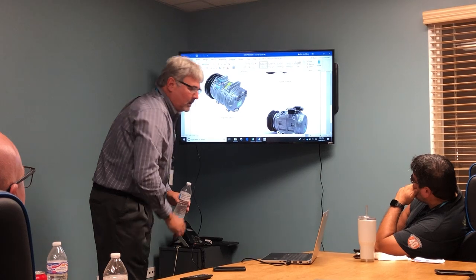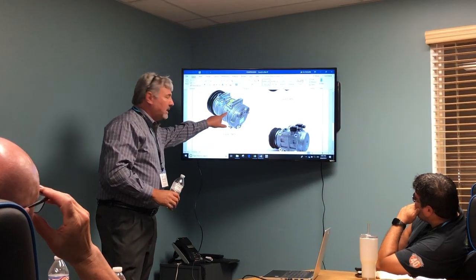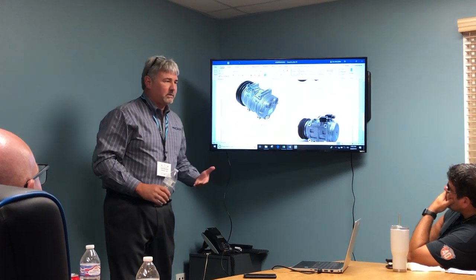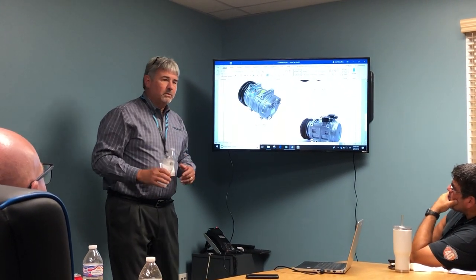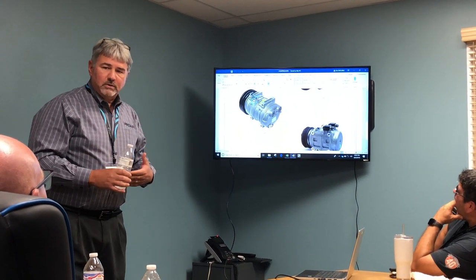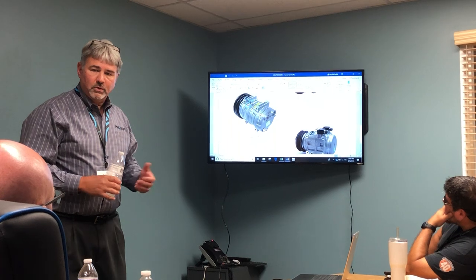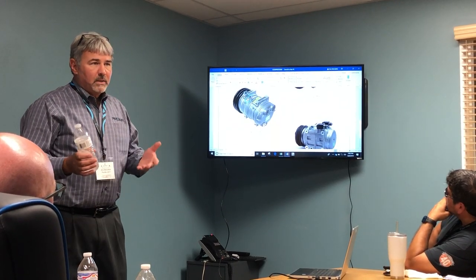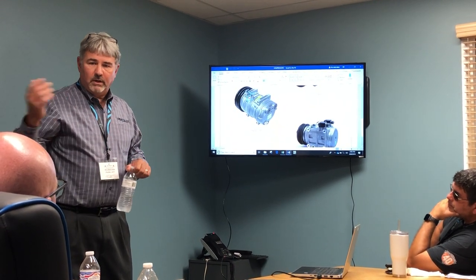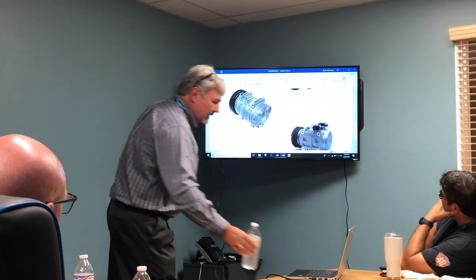In that application, usually a TM16 is most prevalent, which gets you a system rated around 70,000 BTUs. A TM21 takes you to the next step, around 80,000. So you can use the same components and get a little more BTUs out using a bigger compressor and a slightly bigger return or suction line, which moves a little more refrigerant. On a hot day in Colorado, probably 75,000 is good; in a different climate like Texas, 80,000. Those are some of the compressors in the industry.